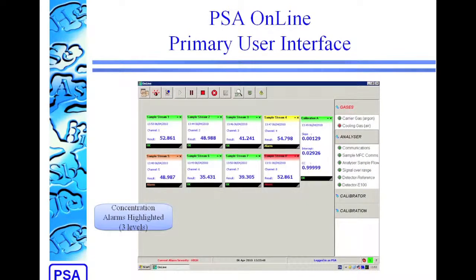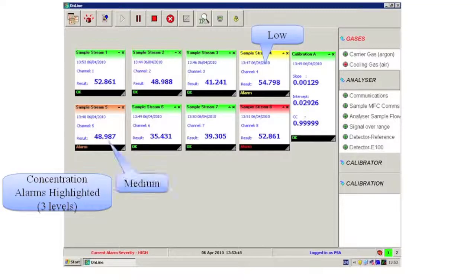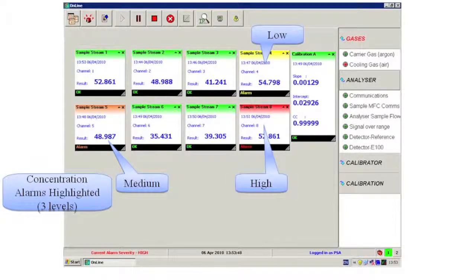The results panels can be set up to show three different alarm levels. They'll be green when the concentration is within the expected range, and they can go yellow for a low-level user-defined alarm, orange for a medium-level alarm, and red for a high-level alarm.